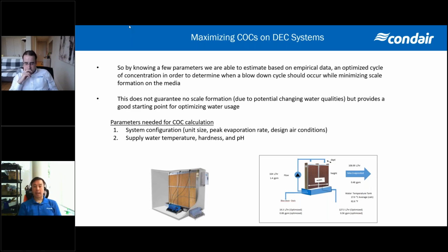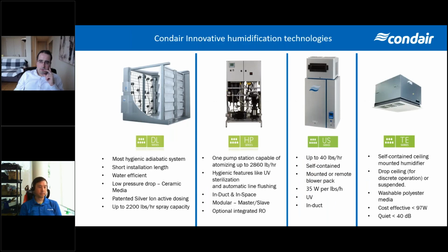If you do have a site where you would like to look at trying to optimize this and look at the media life and water quality, if you have a sample of the water, we can run a sample at a local lab in Ottawa, or if you have a water analysis that's already been done with those parameters that we are looking for, just send those to us and we can run those calculations and give you a pretty good idea of what the maximum COC would be for that system, or potentially what the media life would be on that system if we're running on a fairly hard water system.